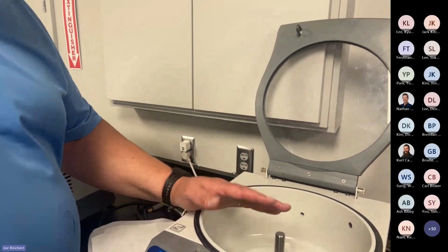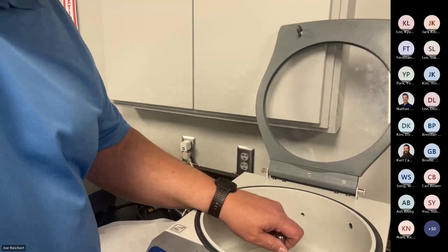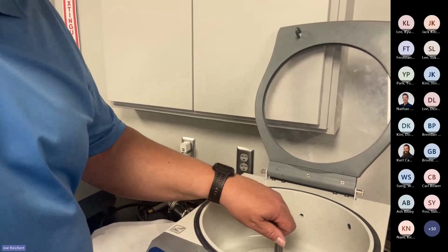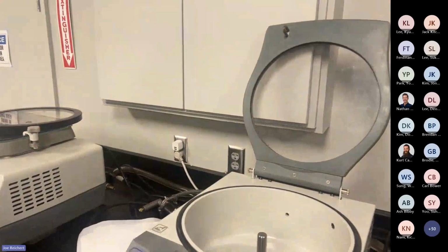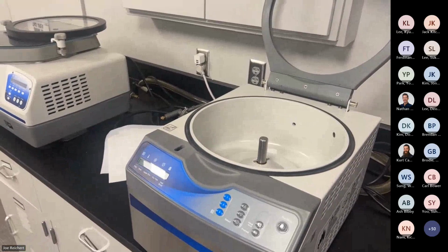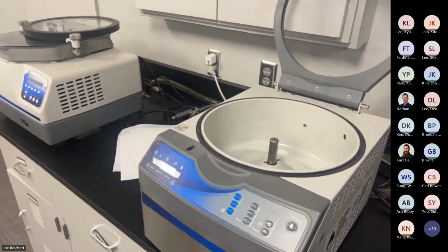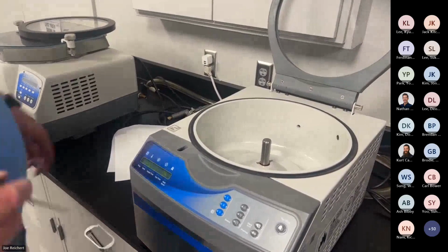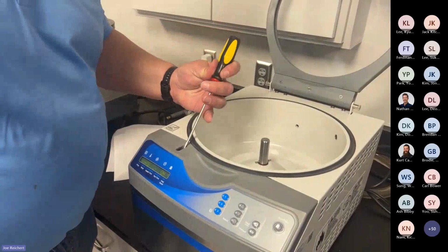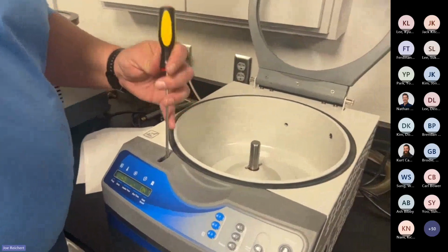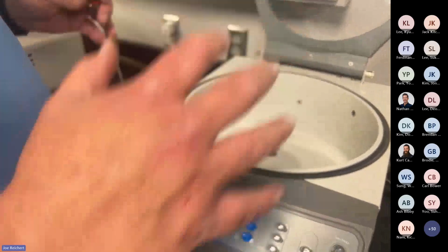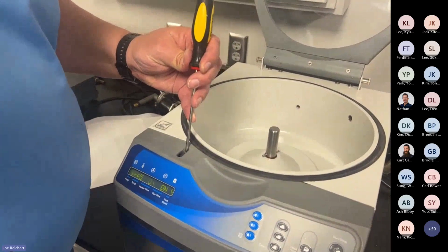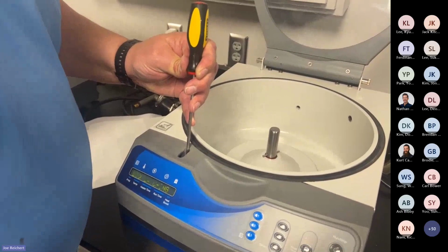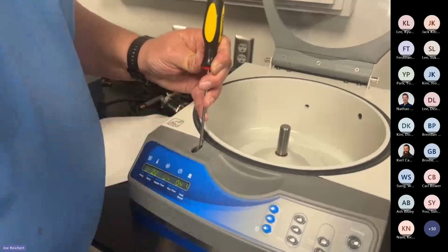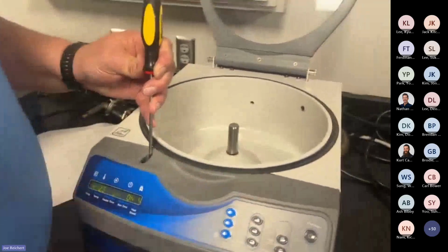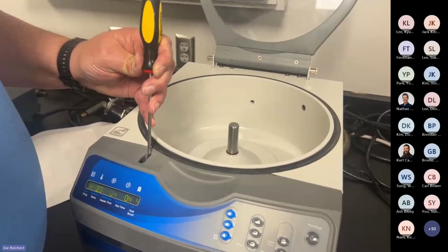So you can hear the cooling fan quit, because that's when the latch is getting ready to close. And you don't even have to have the button pushed in the bottom. If you did that, that would make the whole rotor and everything move. If you just had a small flathead screwdriver and you had your lid up, you could push that button in the bottom if you want to truly see if the rotor is going to turn, but you don't want to have anything in it. Take the rotor out, leave the chamber empty, push the button down with the screwdriver, and then hit run. It says lid latching, rotor's turning, and there's a valve that's going to click, and that's going to turn on the vacuum pump. So obviously the pump's not going to pull the vacuum with the lid open.